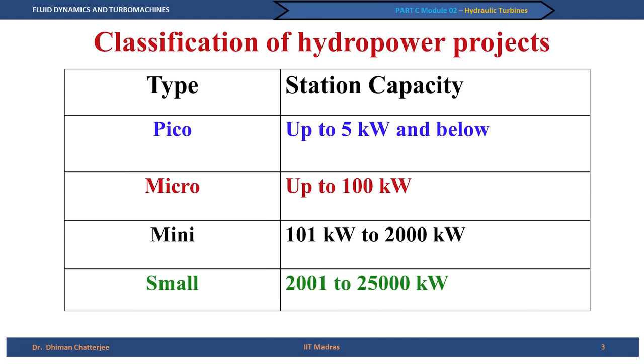In India, pico hydro power projects produce 5 kilowatts or below — basically used for systems where you produce power locally and use it, not really for transmission to the grid. Micro hydro power projects go up to 100 kilowatts. Between 101 kilowatts and 2 megawatts we have mini hydro power projects. Above 2 megawatts and up to 25 megawatts is the small hydro power category, and above that we have large hydro power stations.